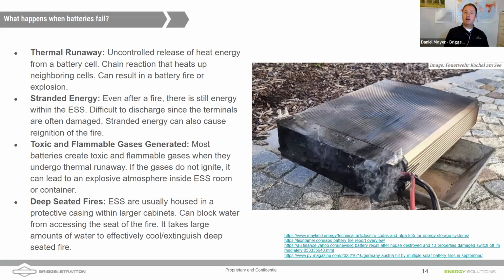We have 9540A that demonstrates this, and I'll talk about it a little later. We have to force the battery into thermal runaway and then watch what happens. But even after the fire, there's still potential energy stored in these battery cells, and it can be hard to discharge that if you can't access the conductors, or if the battery management system has opened up a contactor. So what that can lead to is reignition.